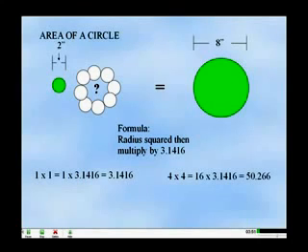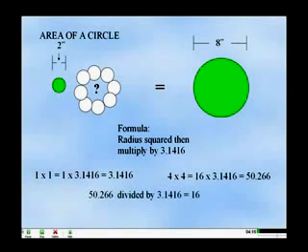Likewise, an 8 inch pipe has a radius of 4 inches. Now square the 4 by multiplying it by itself: 4 times 4 equals 16, and then multiplying that number by 3.1416. That equals 50.2656 square inches. To then find the number of 2 inch pipes required to equal the area of the 8 inch pipe, divide the 50.2656 by 3.1416, and you'll see that you need 16 two inch pipes to equal one 8 inch pipe.